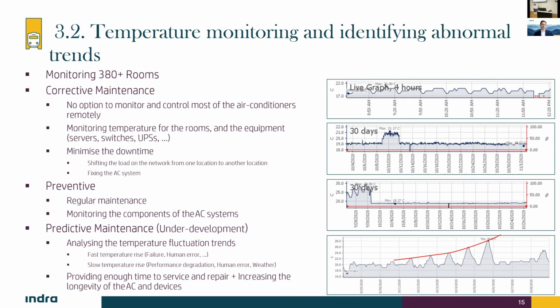For example, let's say you have a storage system in one of these rooms. The cost of that system can be up to $100,000 - these are real figures - and you don't want that system to die. It's very expensive, and temperature is one of the key factors for that system to fail. If you constantly have high temperature in that room, still below the threshold, it can decrease the longevity of the system. When you see the trend going up and down over 2 or 3 weeks, you can plan ahead - for example, increase the capacity of the air conditioner in that room.